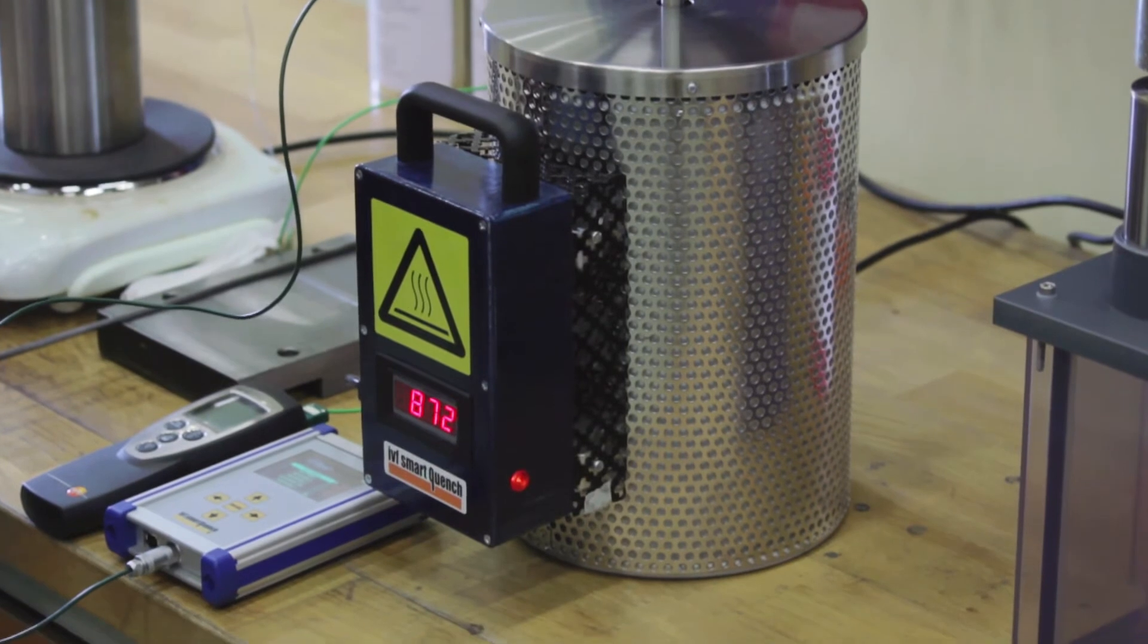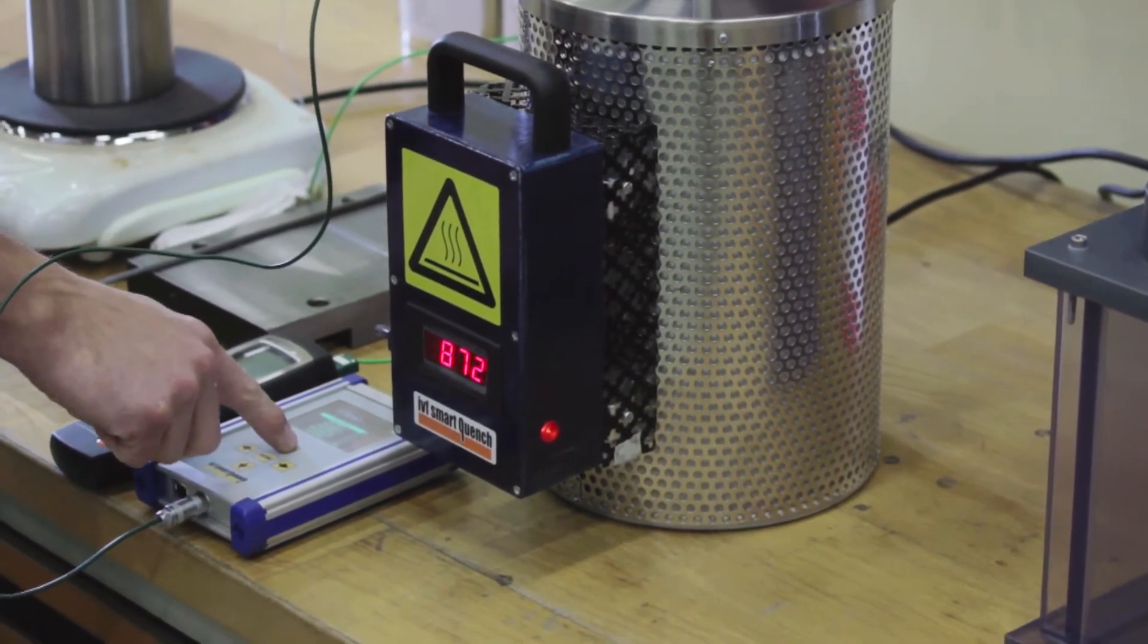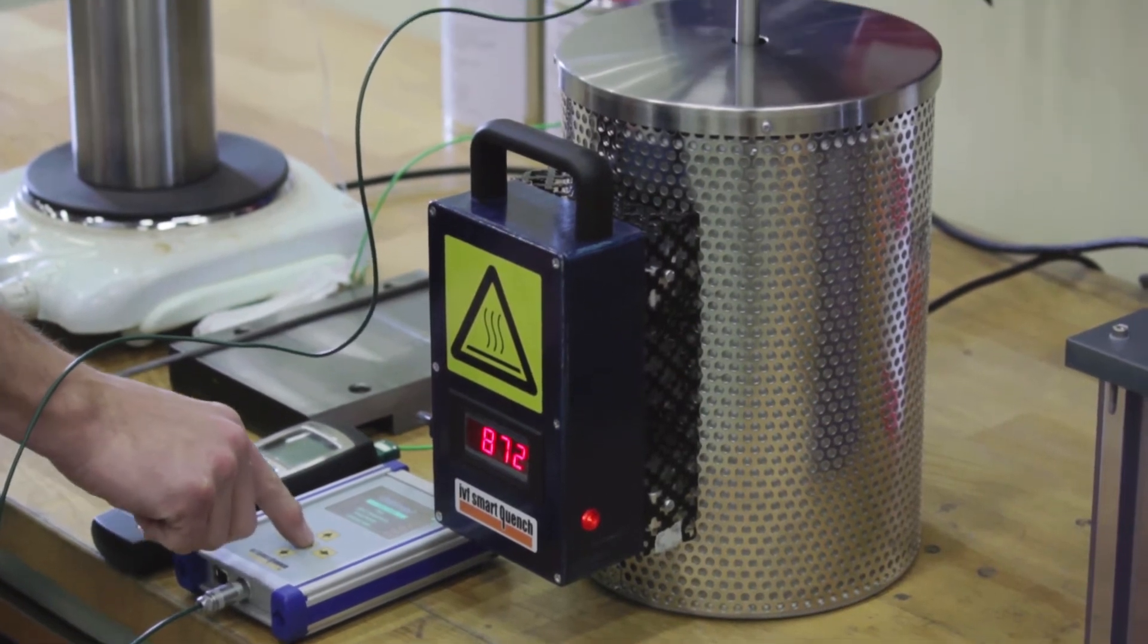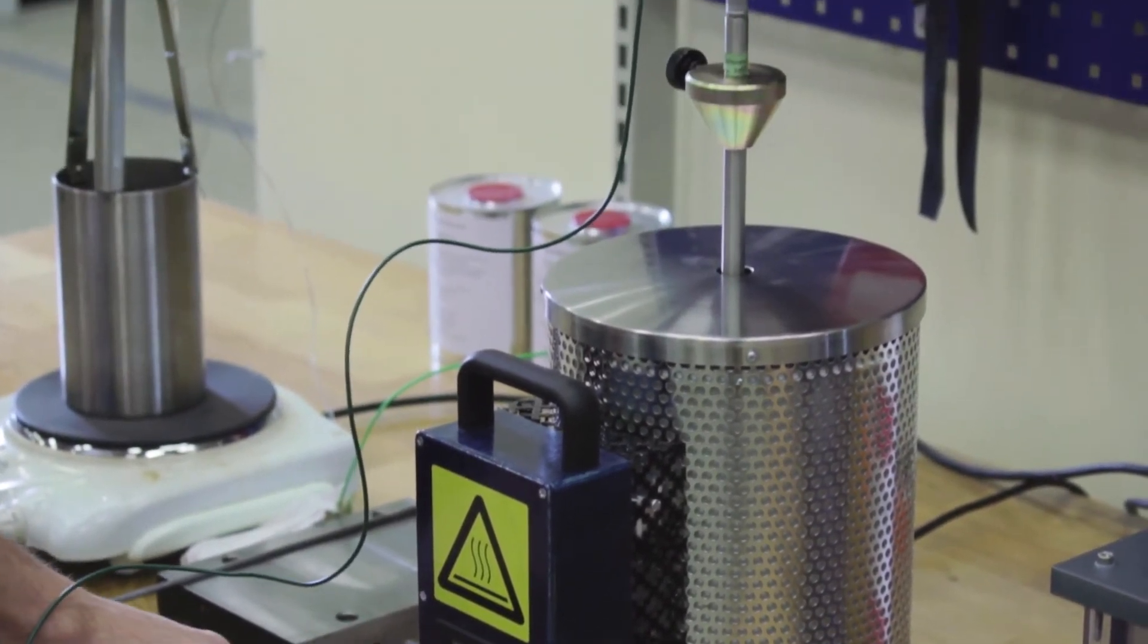Prepare the beaker with the correct amount of oil and check that the cone is mounted at the correct height of the probe. If you are uncertain, check the manual for our recommendations.